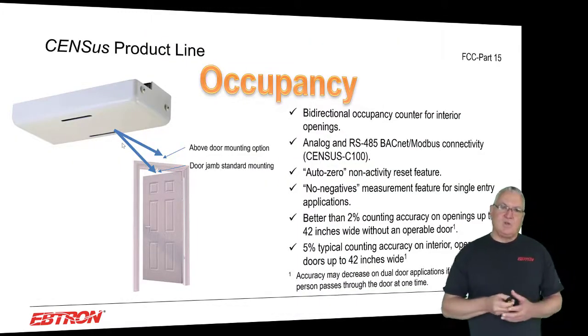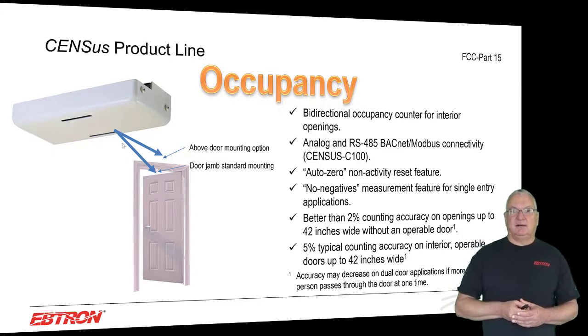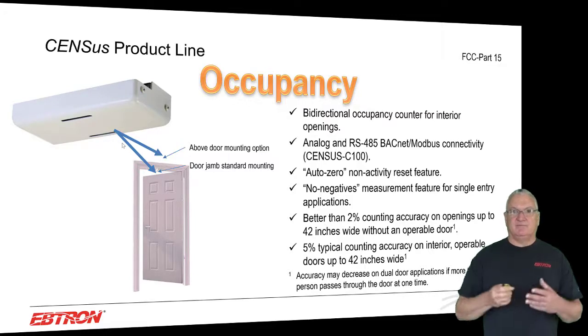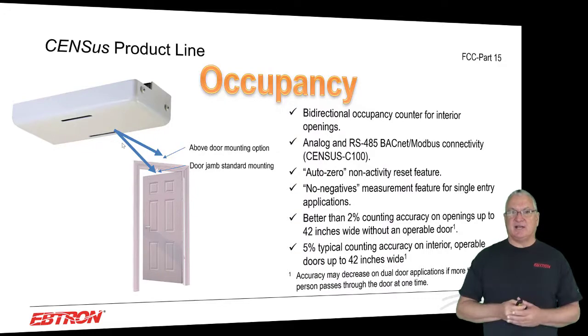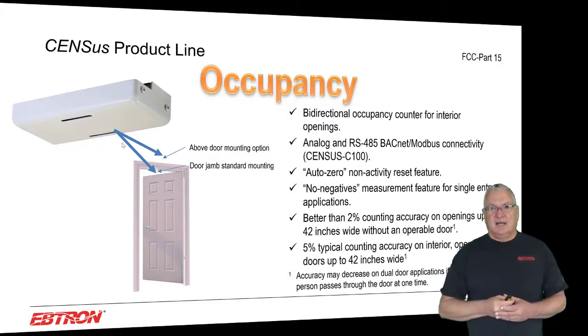Occupancy, we have the CENSus product line. It's a really good product, and not enough people have really taken to it, and I don't really understand it. It's a bidirectional occupancy counter for interior openings. It has two outputs. It has an analog output and RS-485 BACnet Modbus connection. I actually like using it with the RS-485. I think it makes more sense.